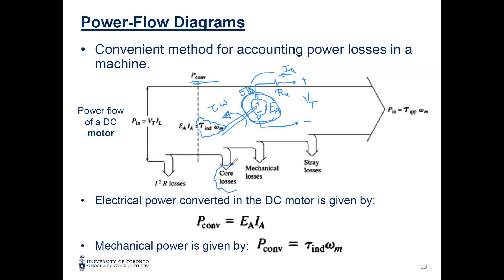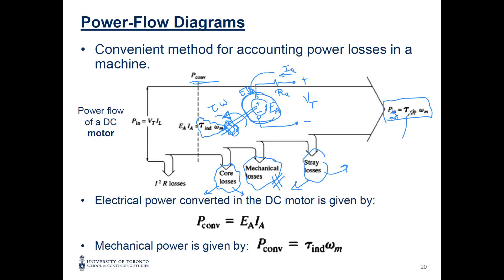After the converted power, we have core losses: hysteresis and eddy current. Then mechanical losses because the machine is rotating — we have bearings causing friction and air resistance called windage. There are also stray losses to balance the equation. At the end you have the output torque, which is different from the induced torque. The induced torque is on the shaft before losses; the output torque is lower.